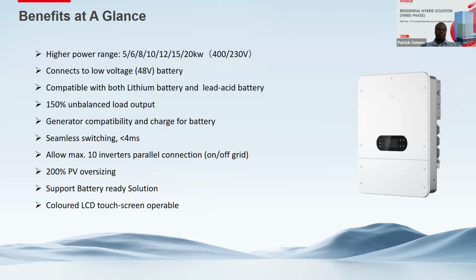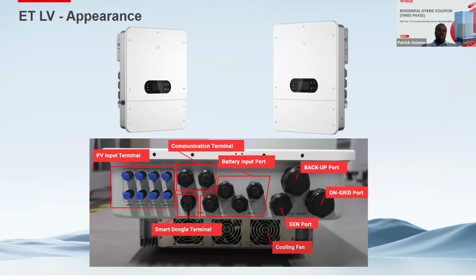And apart from the technical benefits, you can actually see how the ETLV looks. It's sleek, it's compact, and comes with an LCD screen at the front. For the connection of the cables, the airflow is from the bottom. You can see the ports for the PV. It's a hybrid inverter, so we have the PV ports and the battery ports. You also have the AC ports for the generator, for the grid side, and for the critical loads, as well as the cooling fans. You have a port for connecting the dongle. So these are the connection terminals that you have for the ETLV.